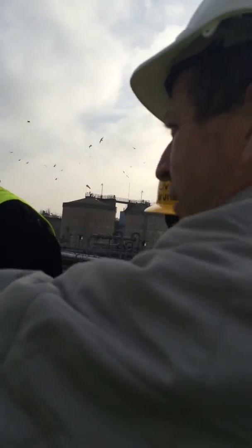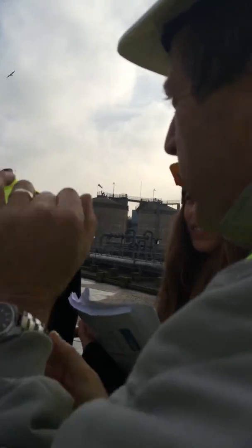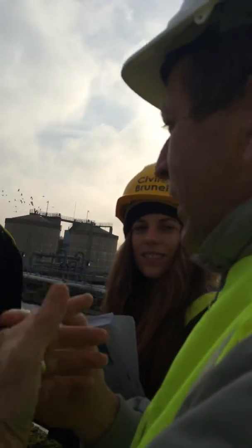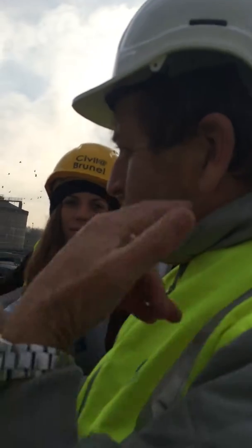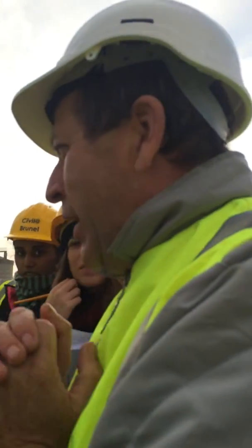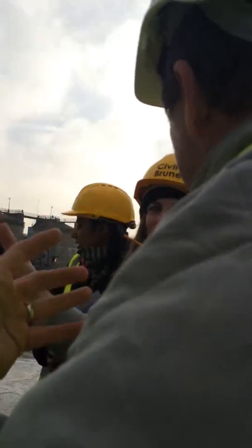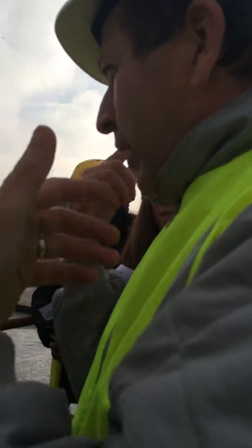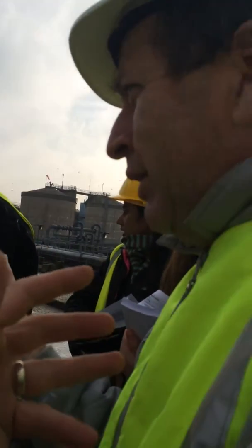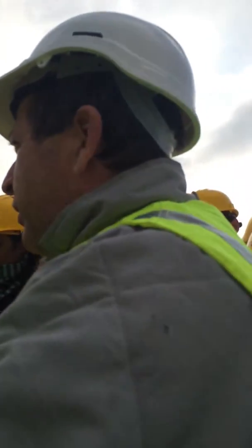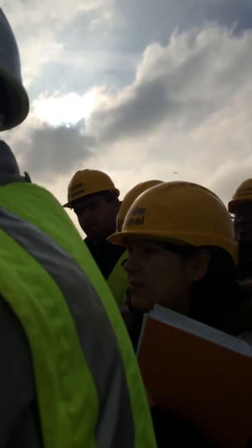The first thing it sees here is the anaerobic zone. The anaerobic zone has got no dissolved oxygen in it at all, and the biology now has to respire, or try to respire, and survive in anaerobic conditions. It has a very clever adaptation where it's able to do that. I won't go into details about it, but that enables the first part of the phosphorus removal process. So the anaerobic zone is there to select bacteria which can survive in anaerobic conditions, and one of the key functions of those bacteria is that they're able to remove phosphorus from the wastewater.